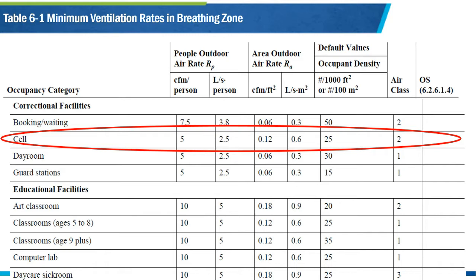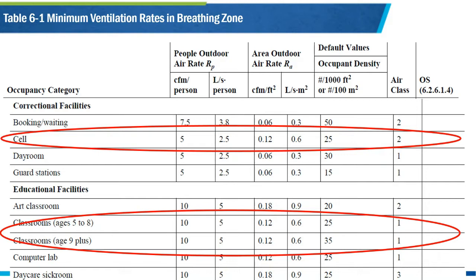For a classroom, this table is showing a minimum ventilation rate of 10 CFM per person, or double the amount of air per person in a correctional facility, with the same 0.12 CFM per square foot of space, and a maximum occupant density for ages 5 to 8 is 25 people per 1,000 square foot, and for ages 9 and up, that density increases to 35 students per 1,000 square foot of space. Could this be a reason we're seeing COVID outbreaks in prisons and jails because of the difference in ventilation rates?